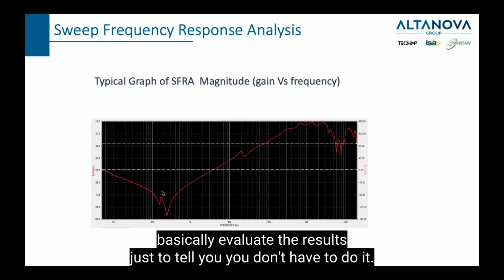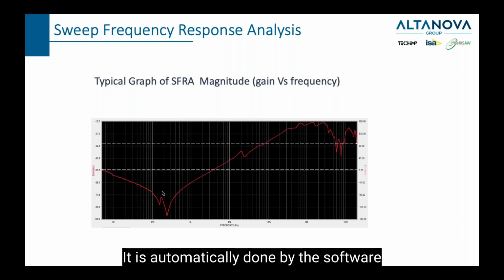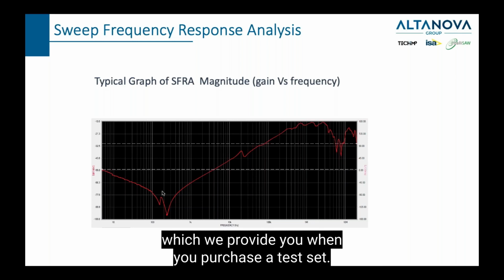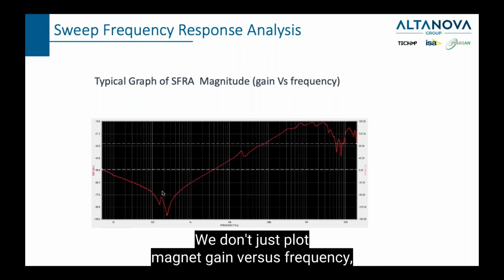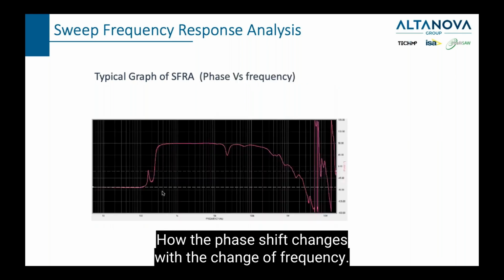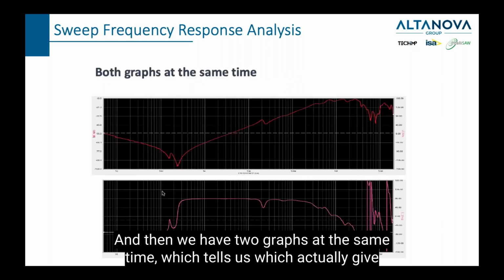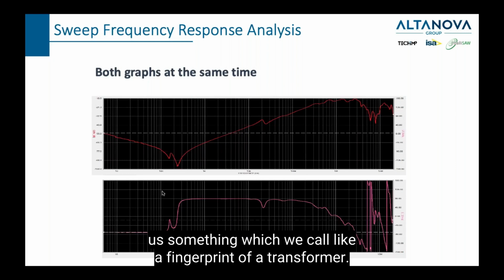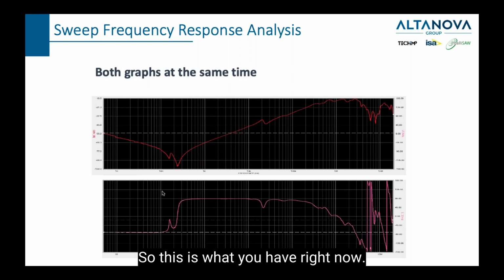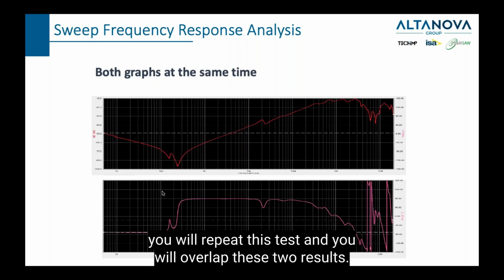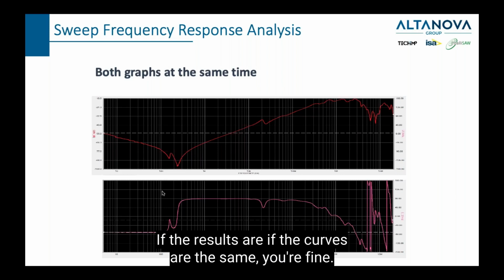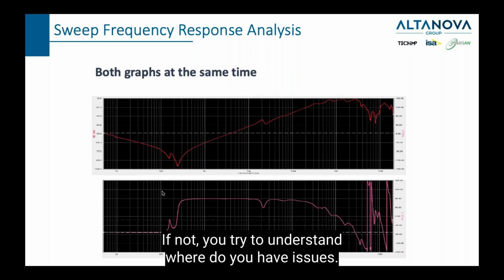So, just to tell you, you don't have to do it. Actually, you don't do it. It is automatically done by the software which we provide you when you purchase a test set. We don't just plot magnitude gain versus frequency, we also plot phase versus frequency, how the phase shift changes with the change of frequency. And then we have 2 graphs at the same time, which actually give us something which we call a fingerprint of a transformer. So this is what you have right now, and then if something happens, you will repeat this test and you will overlap these 2 results. If the curves are the same, you're fine. If not, you try to understand where you have issues.